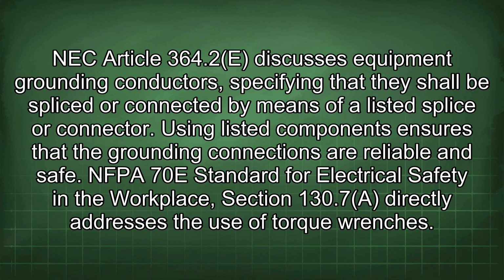NEC Article 364.2(E) discusses equipment grounding conductors, specifying that they shall be spliced or connected by means of a listed splice or connector. Using listed components ensures that the grounding connections are reliable and safe.